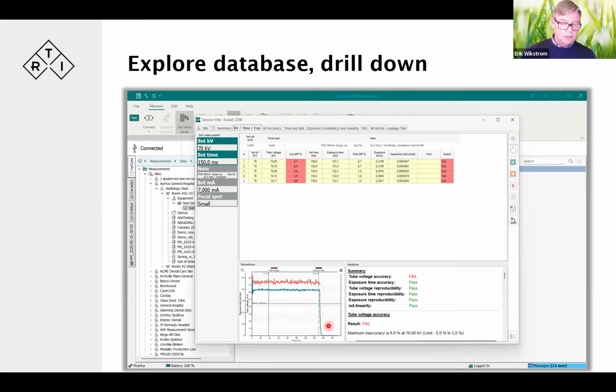That's the possibility of looking at, say, HVL over time. With most instruments now able to do a one-shot HVL, we can follow and see if there's any deterioration in HVL as time passes, or if it's stable for this tube manufacturer. Maybe we need to look at another tube model to see if it gets a flatter line or has a longer expectancy when it comes to HVL — whatever trends you might want to look at.